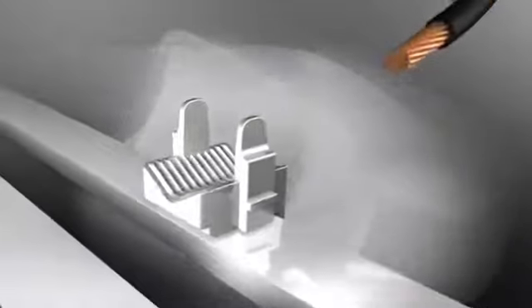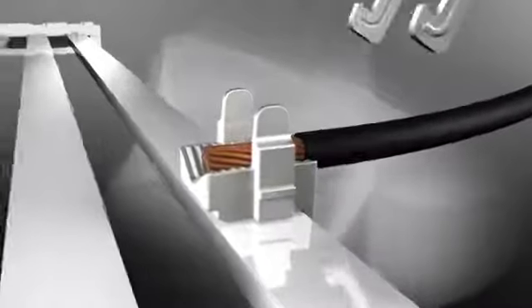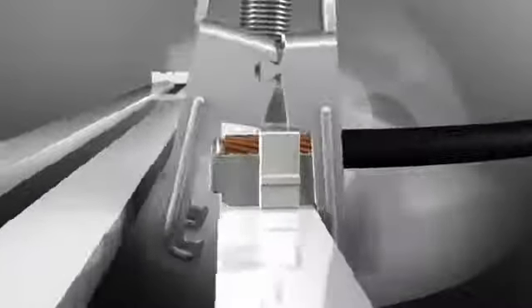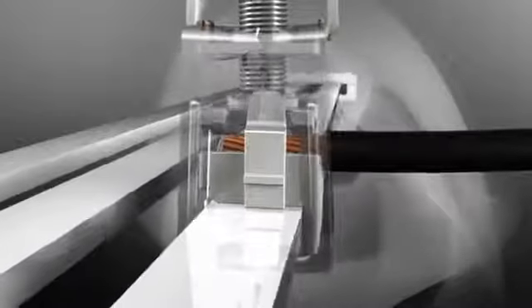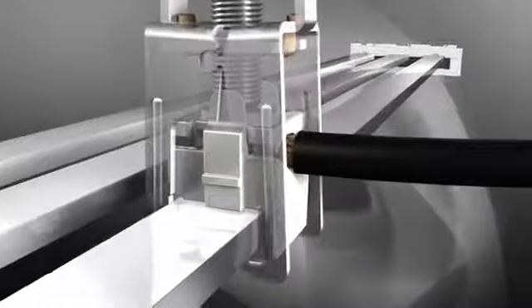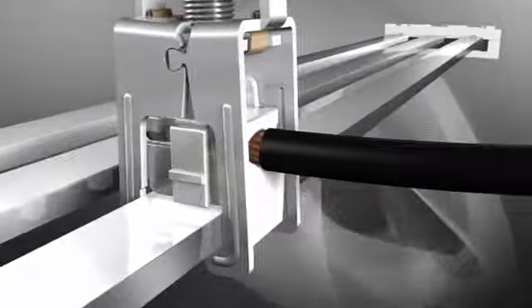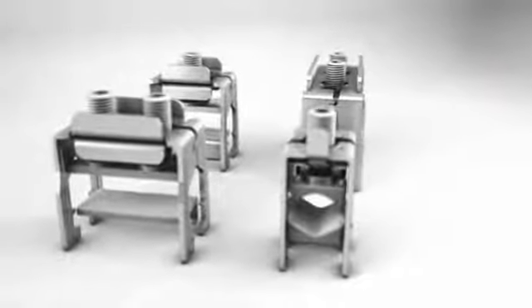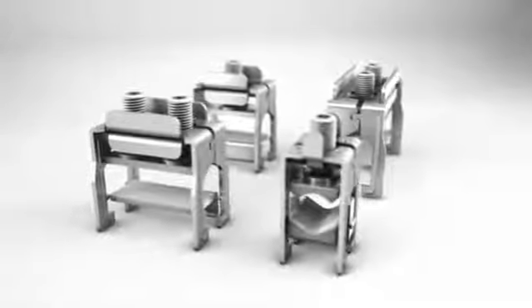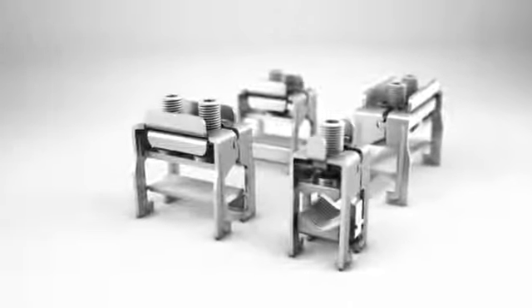Woehner offers sophisticated and flexible connection technologies for cables and flat conductors for a reliable feed to the bus bar systems. Terminals like the Crito Profi clip permit safe and easy mounting of copper and aluminum conductors on the bus bar system. The bus bar does not have to be drilled. No additional nuts, washers, or above all, cable lugs are required. A screw locates the terminal with the conductor securely on the bus bar. This means that even large cross-sections of 300 square millimeters, for example, can be connected with ease. The combination of the individual elements ensures a safe and universal connection, no matter where in the world.